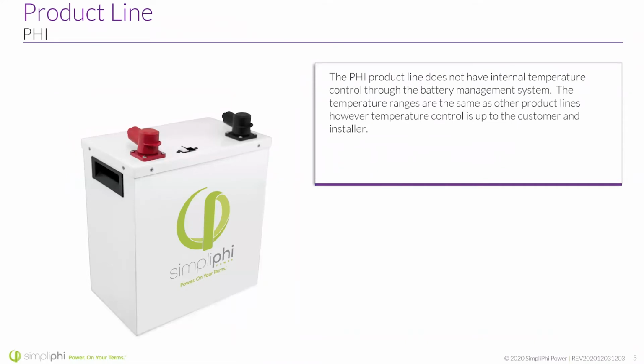So a little bit about the product line and the differences here. Really, I'll just go through the two main differences between our main products here. The Phi product line does not have any internal temperature control through the battery management system. The temperature ranges are the same as the other product lines. However, temperature control is up to the customer and the installer. There's no built-in protection there. It does not have that regulation.